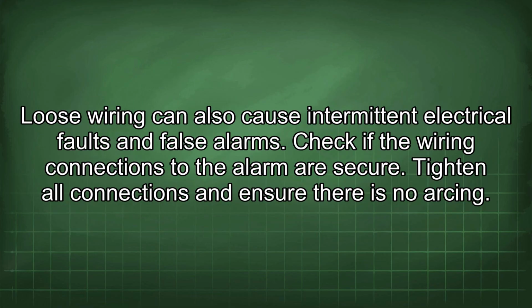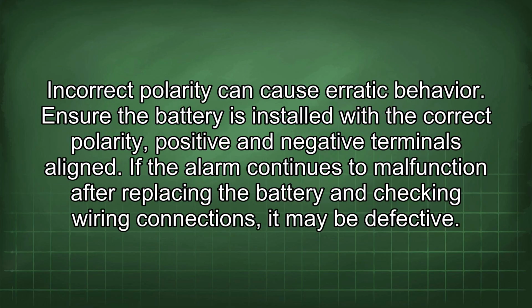Loose wiring can also cause intermittent electrical faults and false alarms. Check if the wiring connections to the alarm are secure. Tighten all connections and ensure there is no arcing. Incorrect polarity can cause erratic behavior. Ensure the battery is installed with the correct polarity, positive and negative terminals aligned.